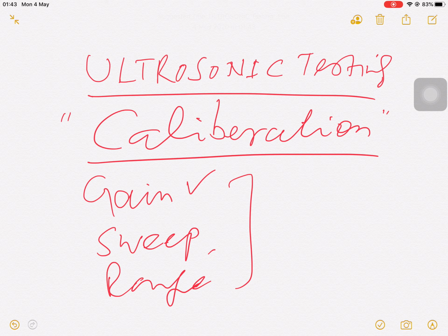So gain settings are normally established by adjusting the vertical height of an echo signal, as I will show you afterward. If you see these specifications, they are based on the echo response from a specific standard reflector in a material similar to that which will be tested.